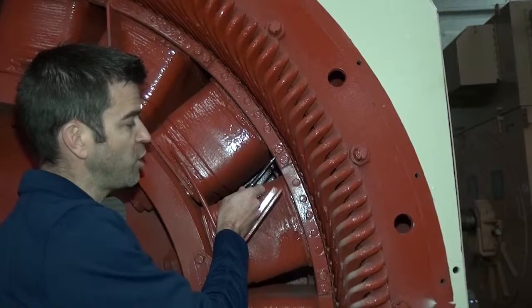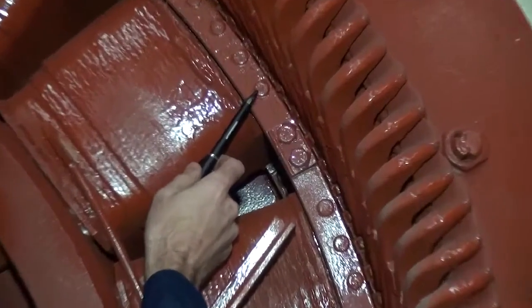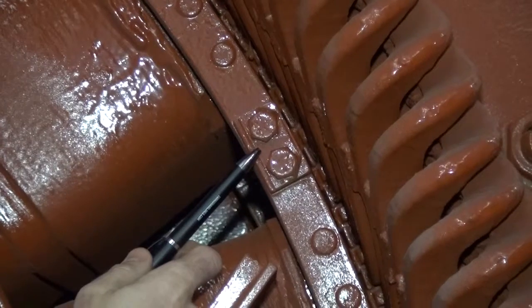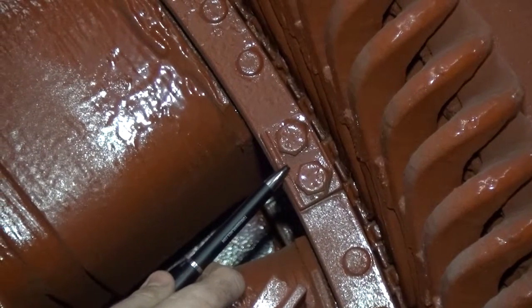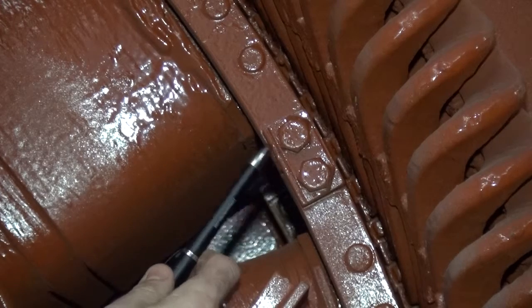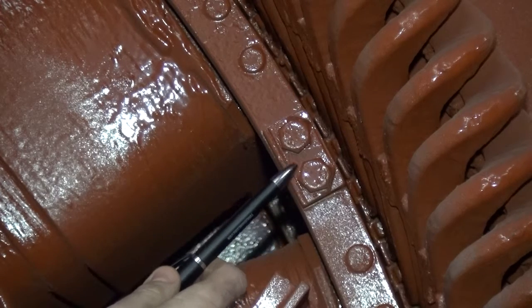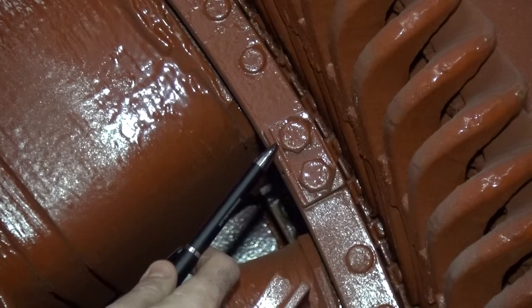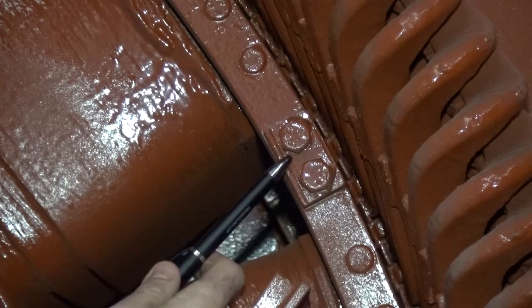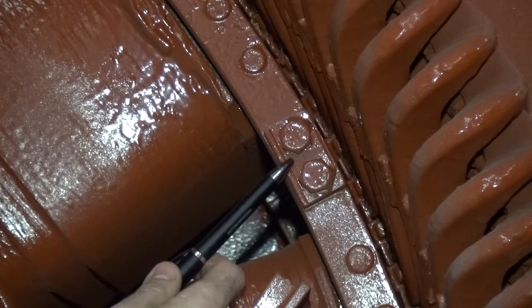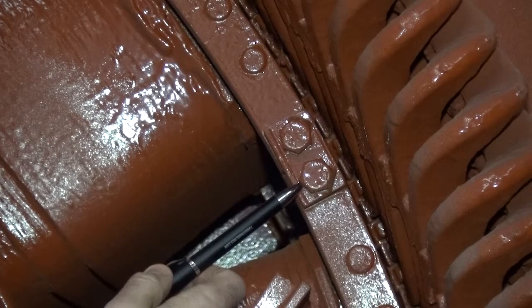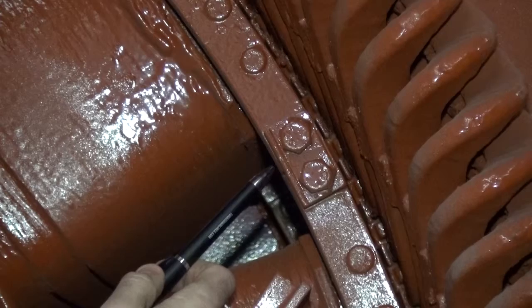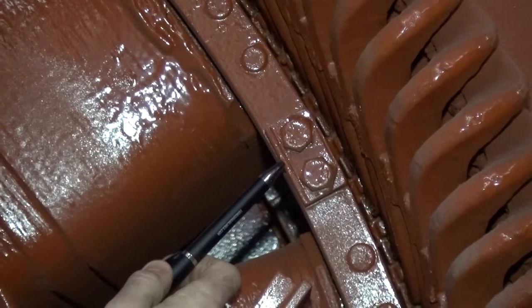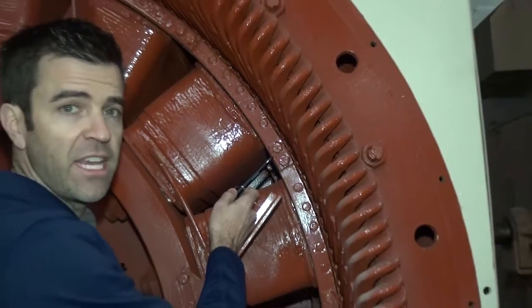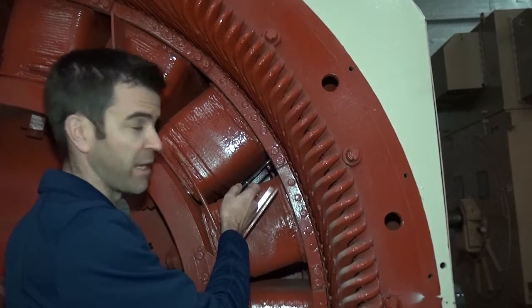Here we have the joint between two of the end rings through which the cage bars are brazed. This joint will pass a large amount of current during startup, several thousand amps, and is subject to a high amount of electrical heating. This assembly is bolted, which is actually not an ideal electric machinery style. Electric machinery tends to use a brazed joint, which is much better at conducting electricity. Carefully inspect this joint for oxidation, overheating, or separation of the joint, as this would dramatically impact the starting performance of the motor. Take pictures of any end ring segments which appear suspect.